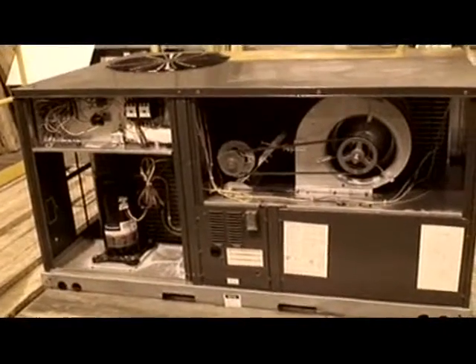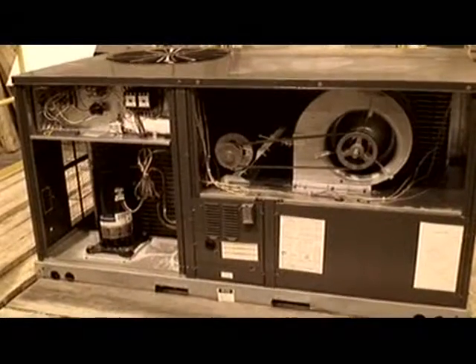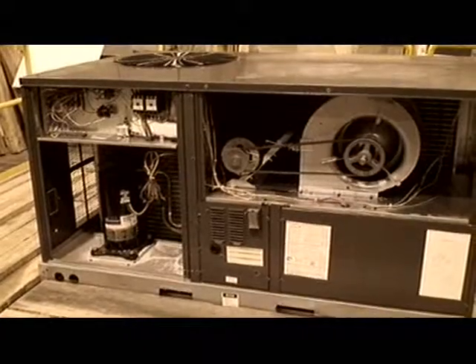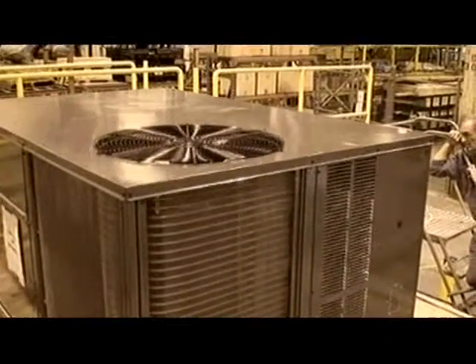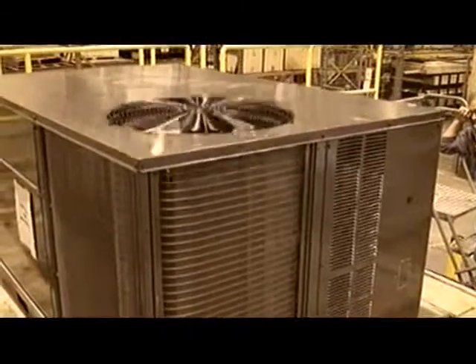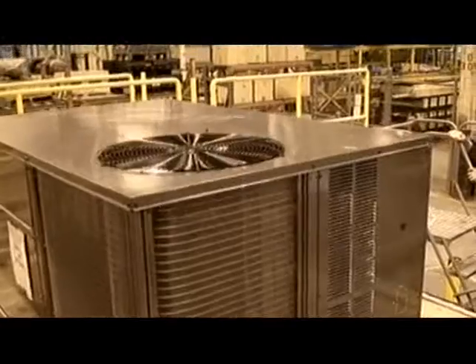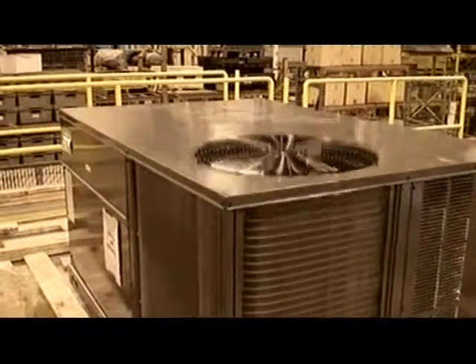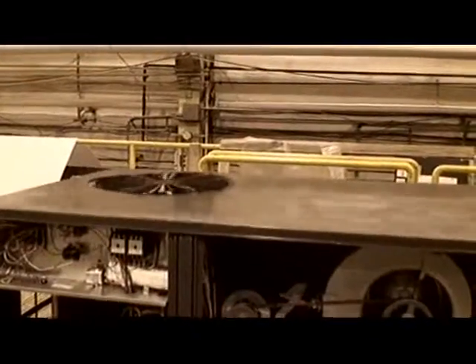What you just witnessed is a bit alarming to us and is not the form of flattery we were looking for. We witnessed the first condenser fan grill screw coming out only after 5 minutes of test time. The second screw came out right after, at 6 minutes, the third after 20 minutes, the fourth at 25 minutes, and the fifth at 32 minutes, and the final one at 35 minutes. All of this led to the entire motor and grill dropping into the condenser coil section.